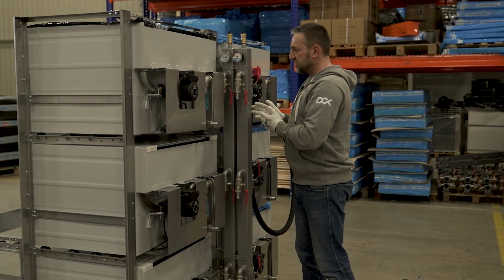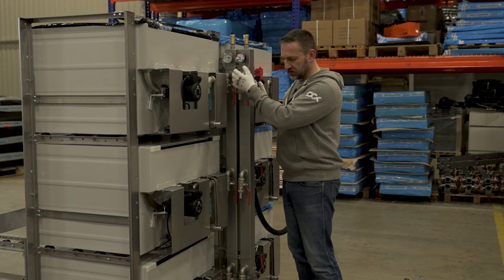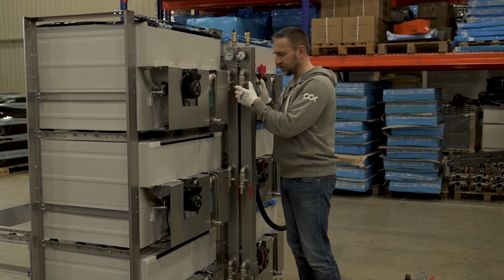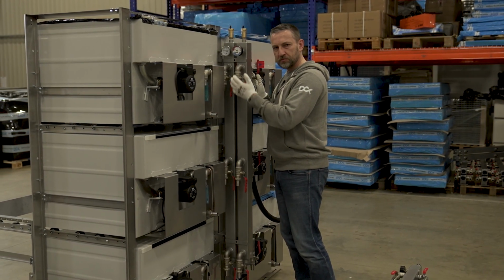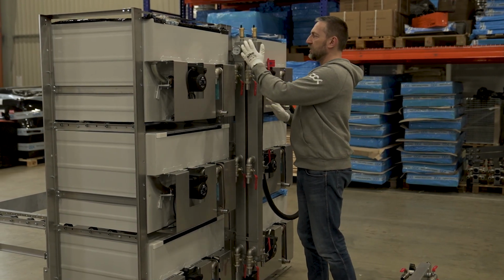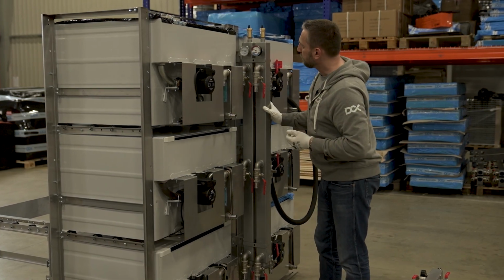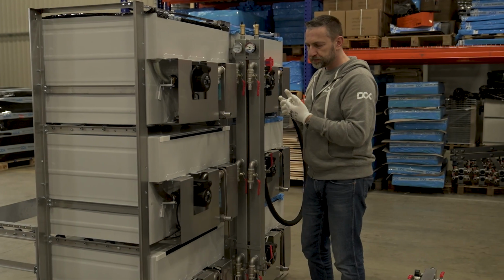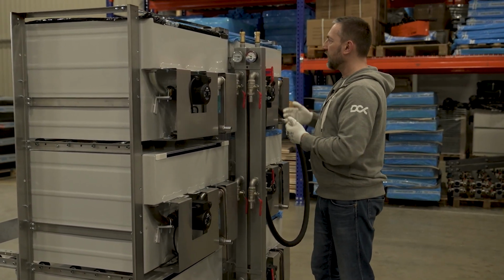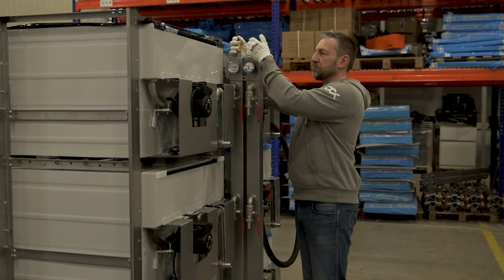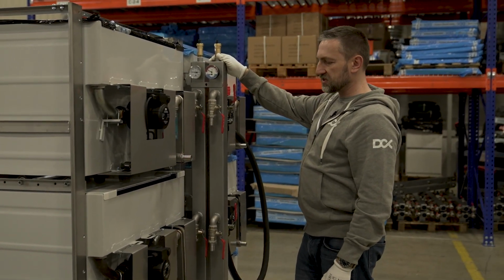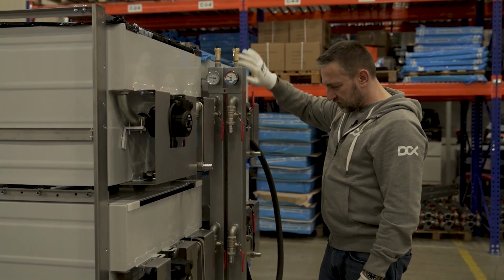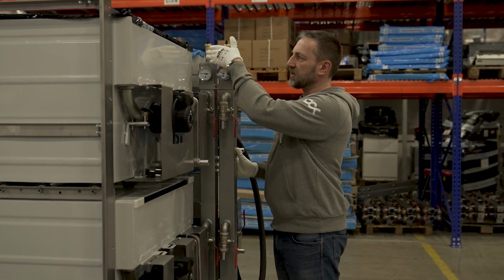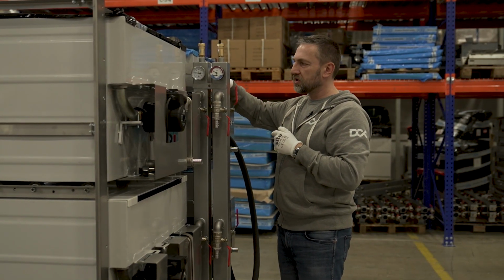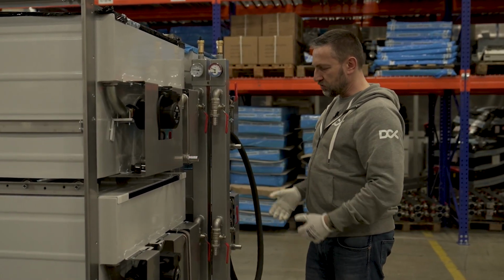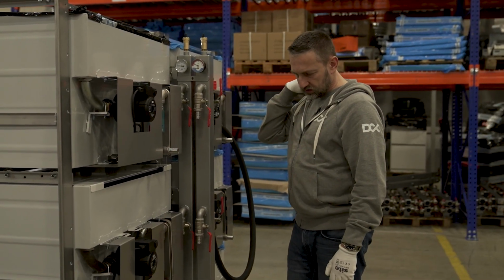The manifold has a few elements. It has elbows to make sure that the hose goes down and is nicely tucked around the rack frames. It has ball valves, so we make sure that we supply only those enclosures which actually work. It has a manometer and thermomanometer to measure the pressures and temperatures on both cold and hot sides, so supply and return. And it has venting valves, so you can vent on both hot and cold side. You can vent the system, which is pretty important in such installations. Now the manifold is a pretty simple element, a little bit heavy, but it hangs on the rack frame, and there are openings here and screws. You can pretty easily position that manifold on one rack or two racks. It will stay like that and will be firmly secured.